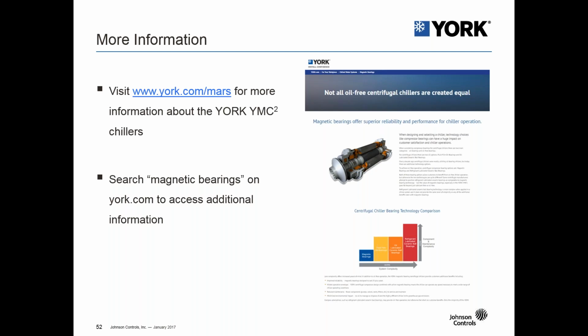All right, we have time for a few more questions. We have one here that's asking, what is the maximum lift capability of the YMC² chiller? So typically what you'd see on a single stage centrifugal compressor would be about 70 degrees of lift, and that's similar to what we see on the YMC². It can handle slightly higher than that based upon the speed and the way that we do our capacity control. But we're also able to use very high entering condenser water temperatures if we have a very high entering evaporator temperature. So the YMC² is also available as a heat pump for installations that can provide an elevated heat source to use that for beneficial heating purposes.